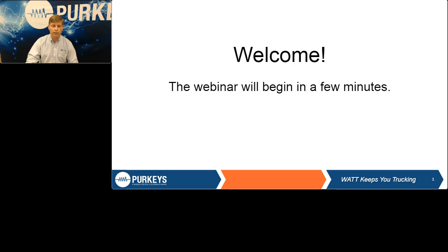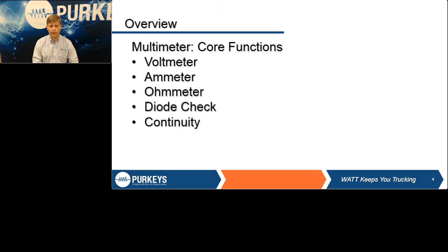So today we're going to talk about multimeters. When we say multimeter, it's a meter that does multiple different things. Some people are very proficient at all the different functions. I visit shops and you'll see a meter that's five years old and still looks new - that's usually a pretty good indicator someone doesn't use their meter. Or you'll see people that only use one or two functions and have no idea what all these other symbols and everything else mean on it. But a multimeter is a voltmeter, an ammeter, an ohmmeter, a diode check, a continuity check. Depending on the meter, it may have frequency, percentage, just all kinds of different things that meter can tell you. And if you don't know how to use them or don't understand what that meter is telling you, obviously you're going to be at a disadvantage.